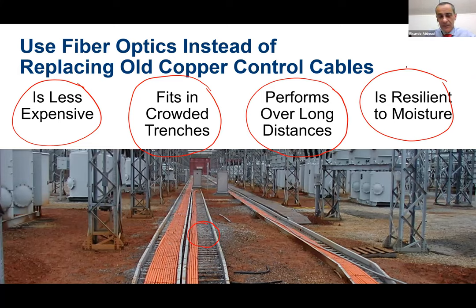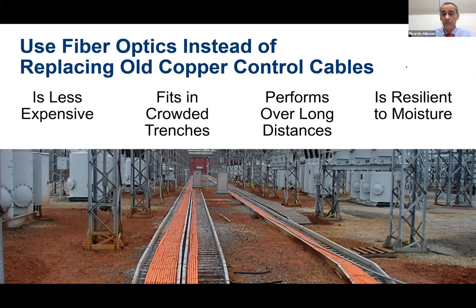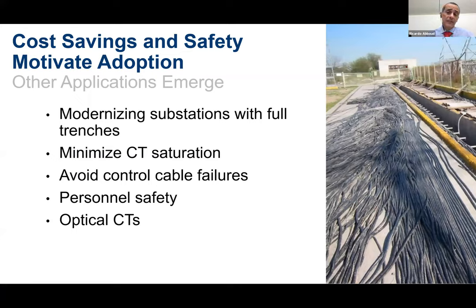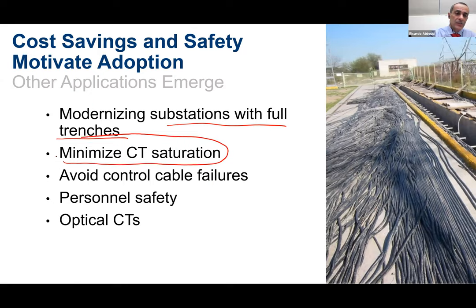So there are a lot of advantages for fibers, and we have some more advantages when using fiber, okay? If it's an existing substation that I'm going to modernize, I can remove all of that copper cables. I don't need to replace that copper cables. So if you already have substations with full trenches, it will be much easier to use fiber than use additional copper cables. Of course, this will minimize the CT saturation, because the copper cable is another burden for the CT. So if you already have some problems with CT saturation, using fiber will reduce this. Much less failures related to the control cables.